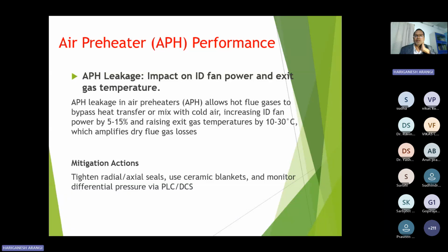where if the APH leakages in the air preheater allow the hot flue gases to bypass heat transfer or mix with the cold air, increasing the ID fan power by 5 to 15%. So that ID fan loading is increasing and raising exit gas temperature 10 to 30 degrees, which amplifies dry flue gas losses. This can be avoided with seal tightness or proper tube welding. So for this, preventive maintenance is required to check any tightness. That is once in a year, 20 days, 25 days, a plant has to shut down and check all these leakages and pressure tests. Then it is better to go for running again.